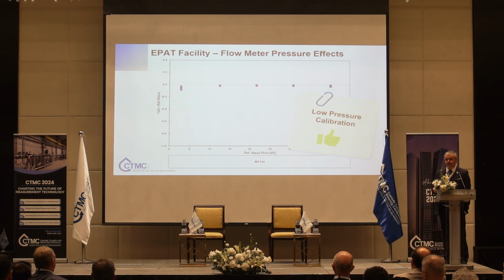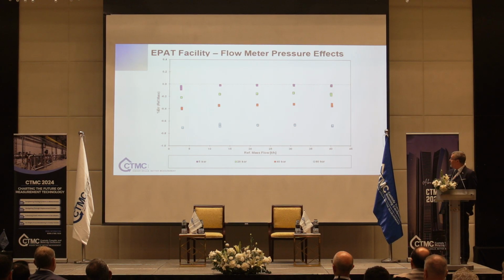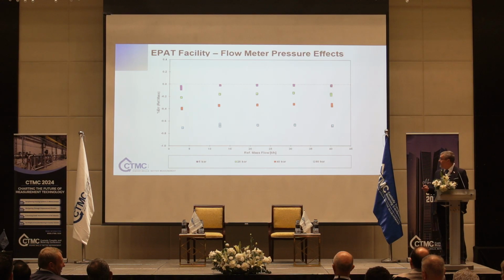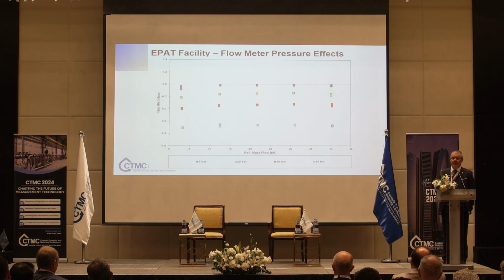What if I change the pressure? I'm now calibrating it at 5 bar, 20 bar, 40 bar and 80 bar. The performance of the meter shifts dramatically. At the 80 bar calibration, which is not an unrealistically high pressure for, say, the offshore industry, the meter's now shifted almost 0.7%. That's way outside the expectations.